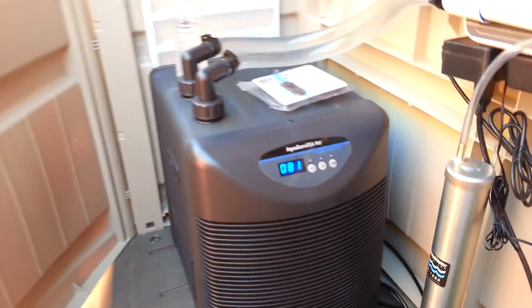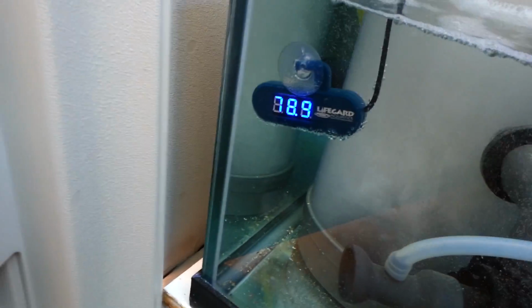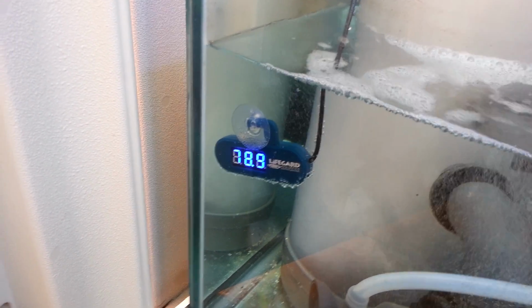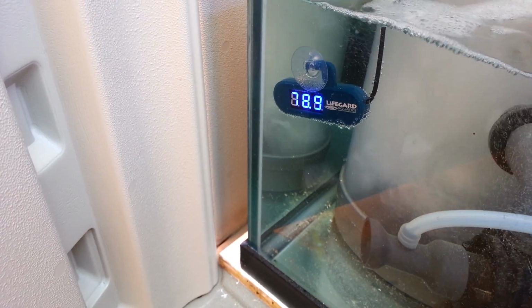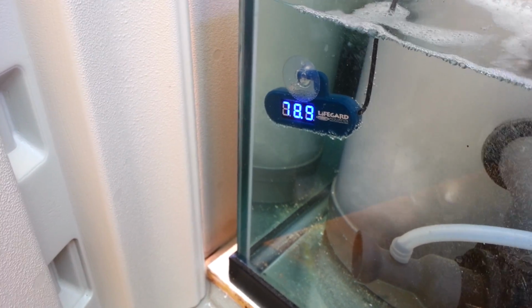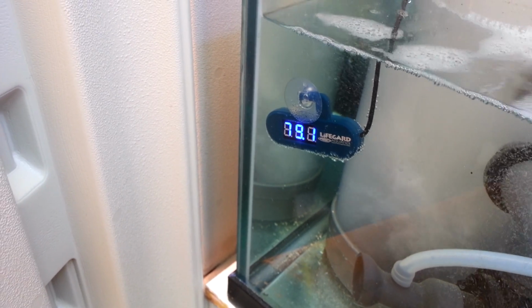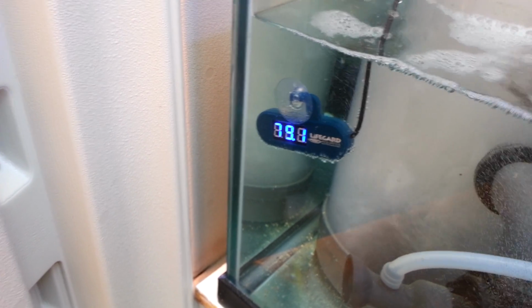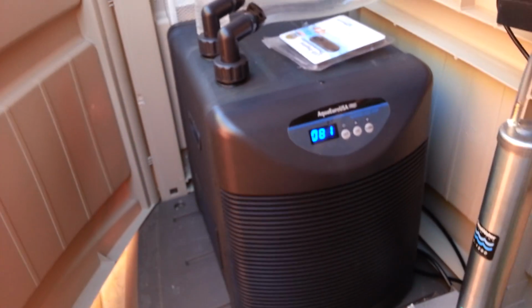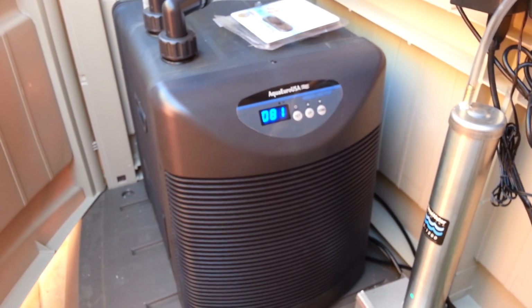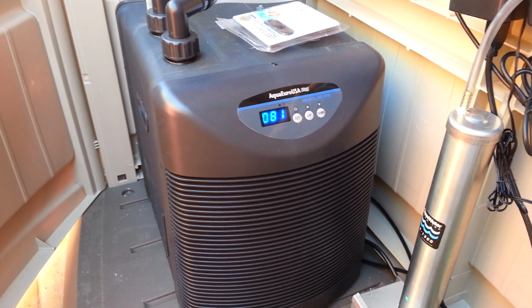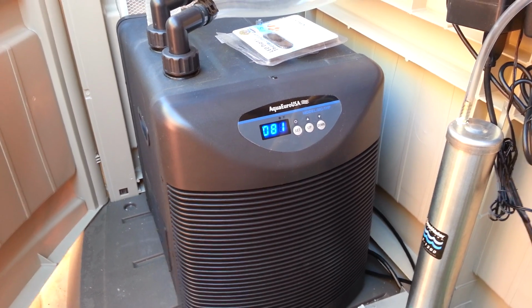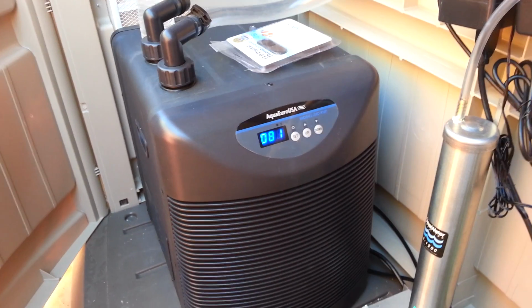The water, let's check on the water in the sump. It's the same as it was. We're maybe 4 or 5 minutes in since the chiller came on. Nothing really changed there, but this has now gone up 2 degrees on this end. Again, really doesn't make any sense.